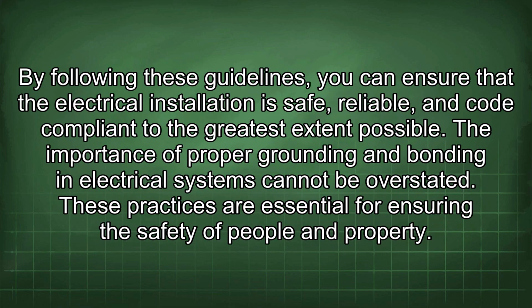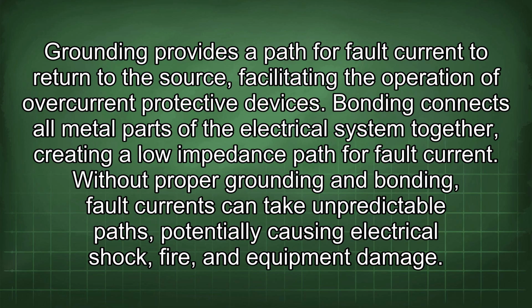By following these guidelines, you can ensure that the electrical installation is safe, reliable, and code compliant to the greatest extent possible. The importance of proper grounding and bonding in electrical systems cannot be overstated. These practices are essential for ensuring the safety of people and property. Grounding provides a path for fault current to return to the source, facilitating the operation of overcurrent protective devices. Bonding connects all metal parts of the electrical system together, creating a low impedance path for fault current. Without proper grounding and bonding, fault currents can take unpredictable paths, potentially causing electrical shock, fire, and equipment damage.